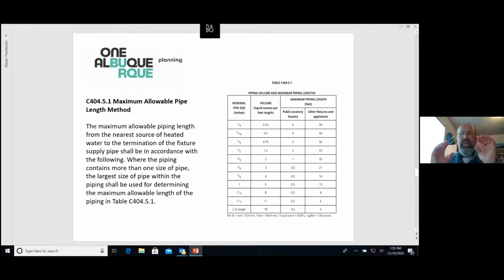Historically, we ran a trunk line down a hallway and branched over to public lavs, you know, run it over and down in the wall and you're good. This is to eliminate that excessive pipe length so you don't have to drain that whole half-inch line down before you start getting hot water. This will, in essence, as I will show you, you're gonna have to pipe over to it and back up and make a loop out of it. Now, if you have a gang bathroom, that's fine. You drop down on the wall, run past them, back up and out. It's a little easier. Now, that's on public lavs.